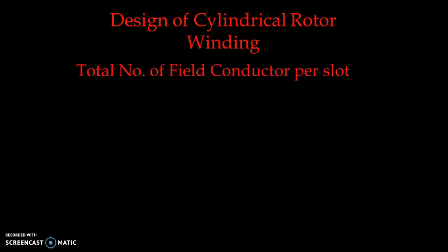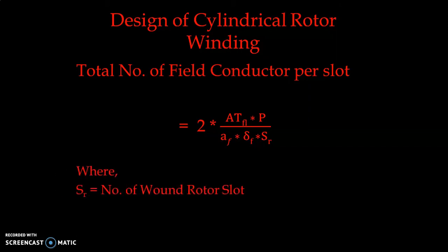Finally, the total number of field conductors per slot is: (2 × ATfl × P) / (Af × δf × Sr), where Sr is the number of wound rotor slots. This completes the calculation of all parameters of the rotor or field winding for the cylindrical type of rotor. In the next lectures we will further design the turbo alternator. Thank you for watching — keep watching, thank you very much.